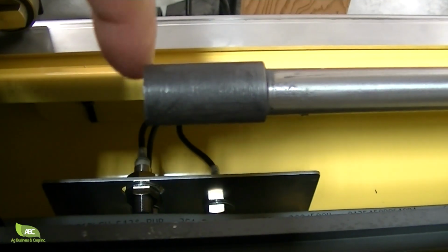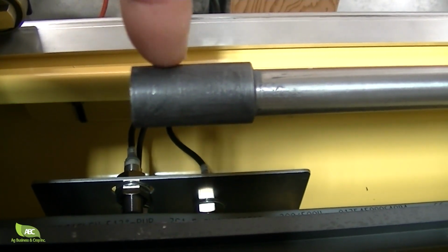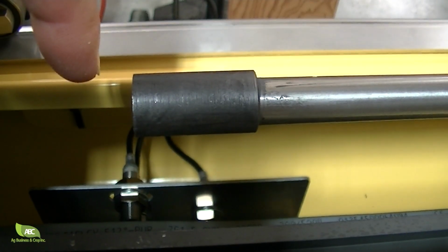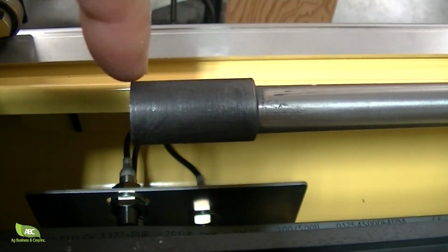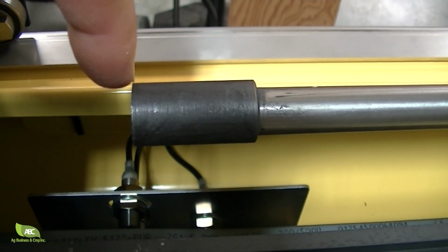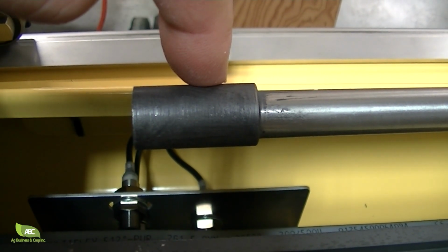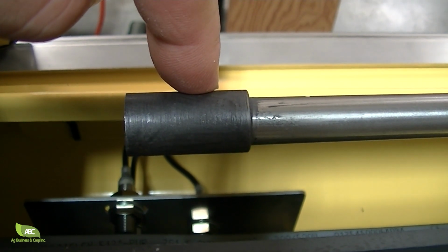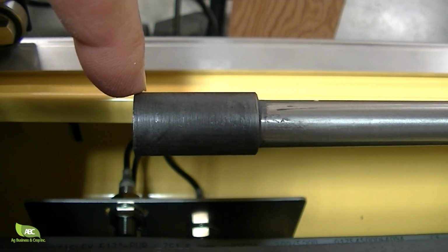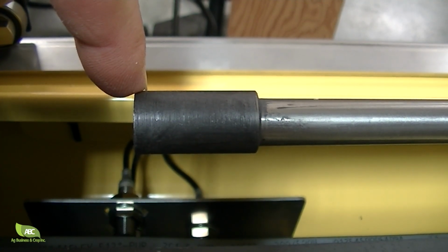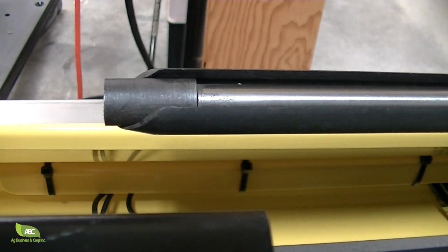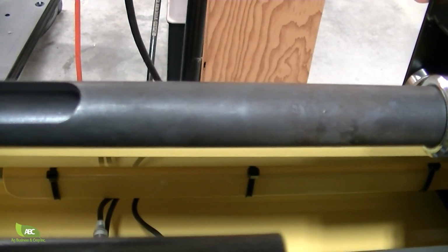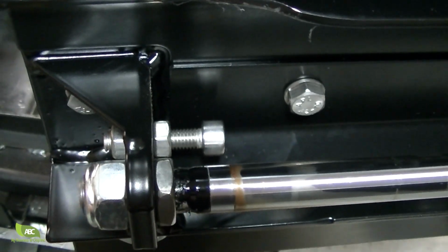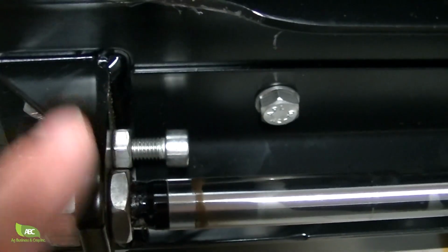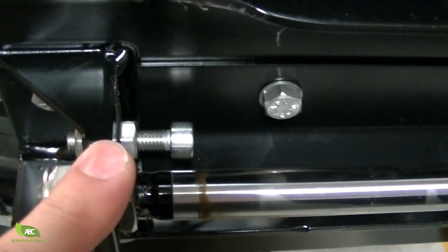And then you can adjust the probe relation with the scraping tip. If it's hanging too low, you lower the screw so the drilling head would stop a little bit higher. If the scraping tip is hanging outside of the probe, you would raise the screw so the drilling head would stop a little bit lower. This way is how you control the scraping tip inside the probe. But once you adjust this once, you don't have to worry about that anymore, unless it got loose during its lifetime, but that's a one-time adjustment.